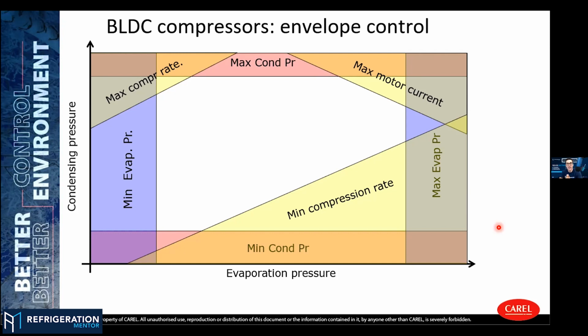So I'm assuming that if it goes into the minimum evaporator pressure for a little bit, it will notify an alarm. Are there alarm settings in the inverter where I can come in? Because the compressor's off because I get a call from, say, an end user and their cooler has warmed up. Is there an alarm setting where it'll say minimum evaporator pressure, to give them an idea of what's going on?